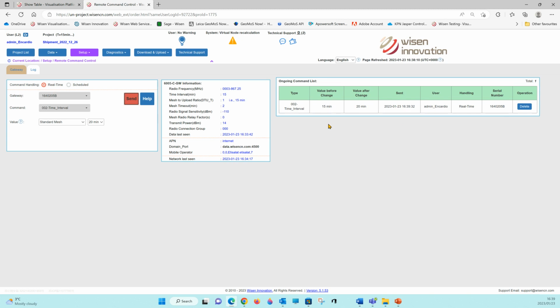So a gateway, when it's 5 minutes and less, is always connected to the phone mast. There's little to no point in it reconnecting and disconnecting from the phone mast. Therefore, a command is virtually an instantaneous action. When you're greater than 5 minutes, then essentially the gateway connects to the phone mast for 2 minutes, then sleeps for the next 13, then wakes up again and repeats.